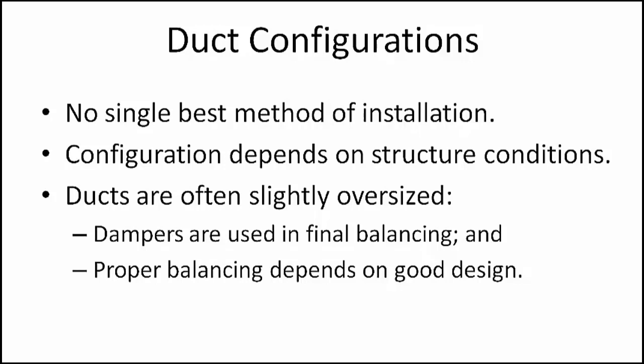The duct configuration selected for use depends on conditions in the structure where the equipment is to be installed. In an actual duct system design, the ducts are often slightly oversized. Dampers are used for the final balancing of the system. Balancing the system is an adjustment process — the air supply to one room is reduced and then that to the other room is increased. The object is to obtain the desired air temperatures in all rooms equally. Proper balancing depends on good design, and a duct system that is easily balanced will show a minimum increase in pressure loss after balancing is complete.